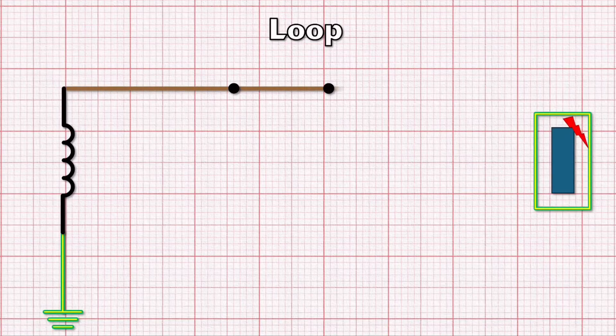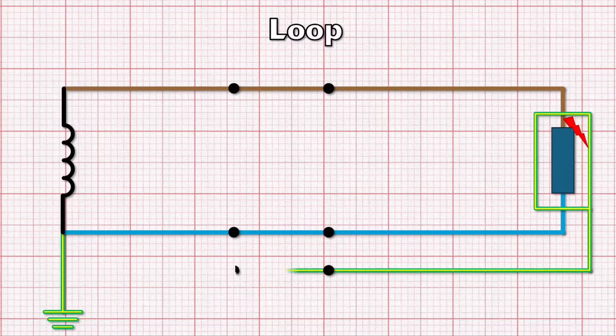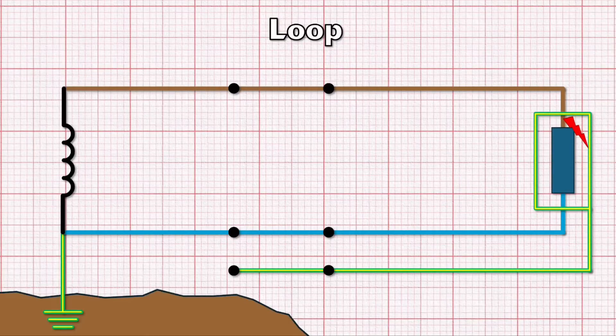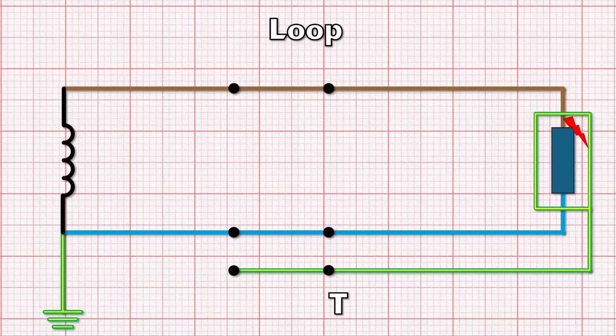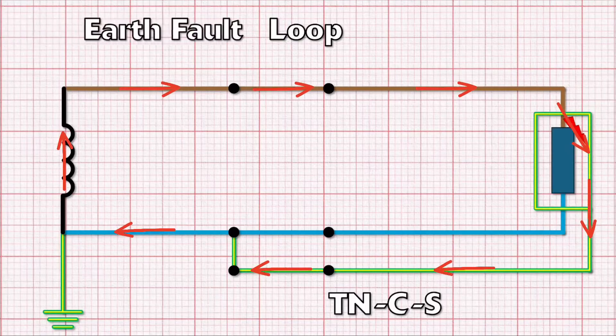the meter tails, any submains, and then the line conductor of the circuit in question. Then there's the fault itself, the CPC back to the main earth terminal, the earthing conductor either to the supplier's means of earthing or the earth electrode, and then the path back to the supply transformer either through the literal earth or through the supply cable. The circuit is completed through the winding of the supply transformer — so you can see it forms a great big loop, hence 'earth fault loop'.